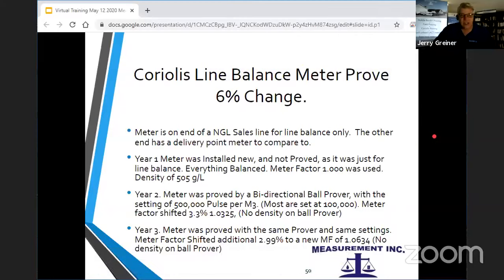So okay, Coriolis line balance meter. There's this line balance meter. It's on one end of an NGL line. It's for line balance only. And the other end of the delivery has a delivery point meter that it's compared to. And this meter was installed new, and it wasn't proven when it was installed. It's just line balance, but they put it in everything. They used a meter factor of 1 and it balanced. The density was 505 grams per liter.